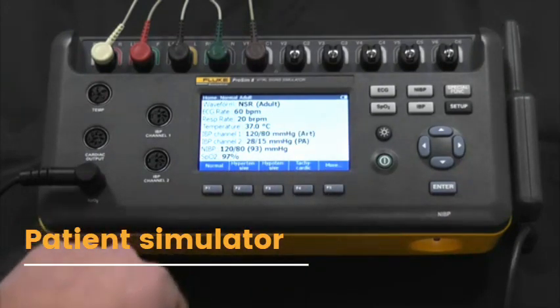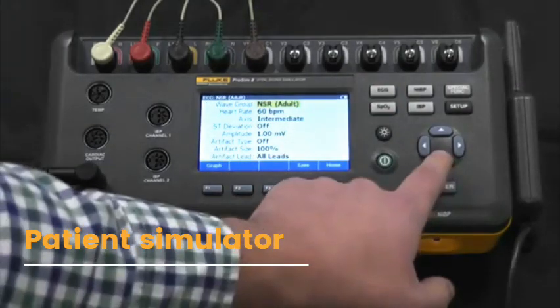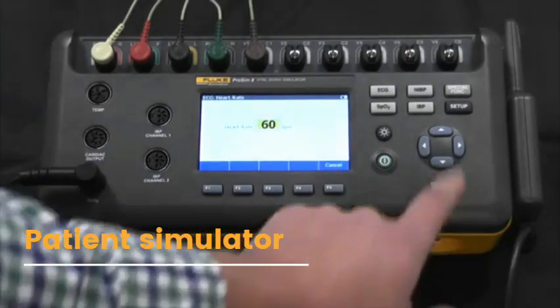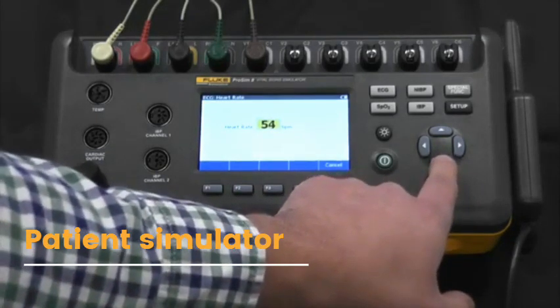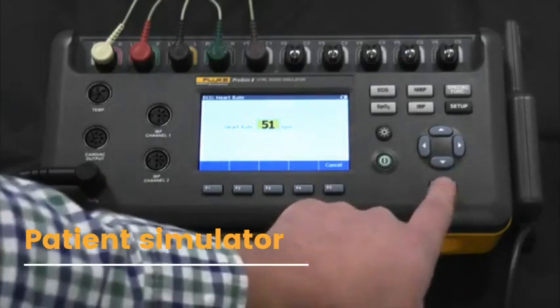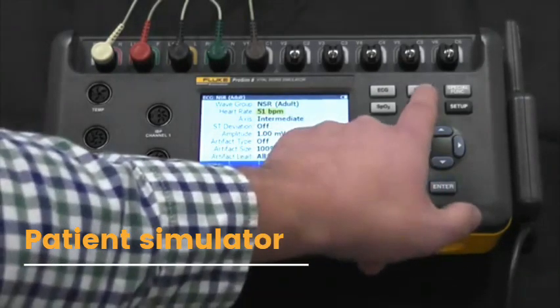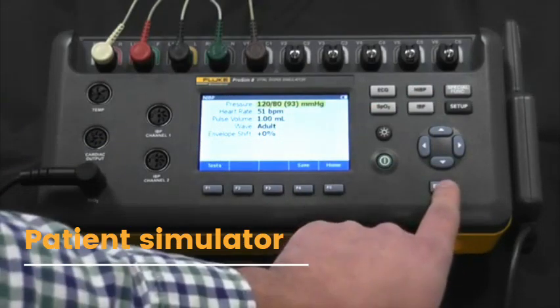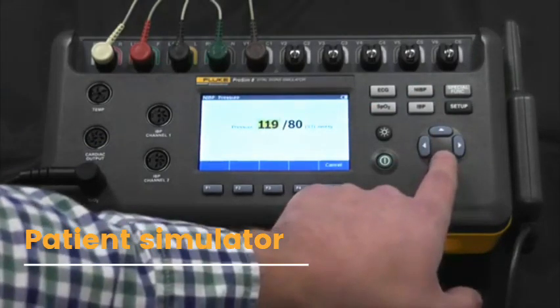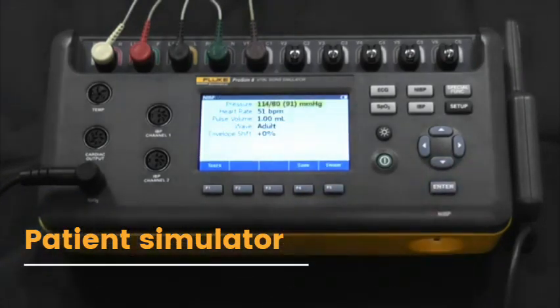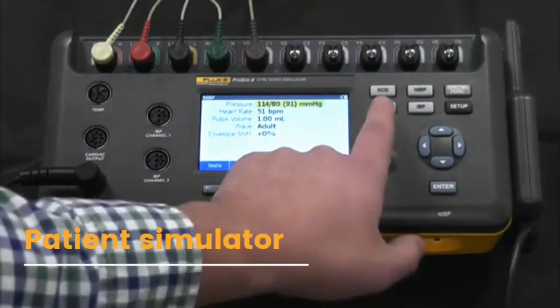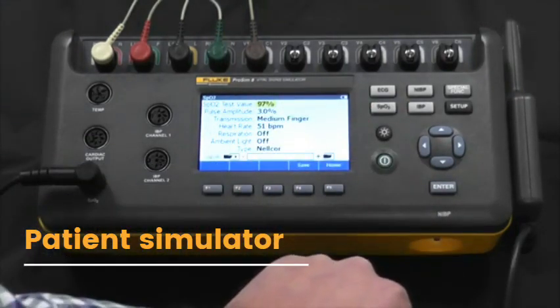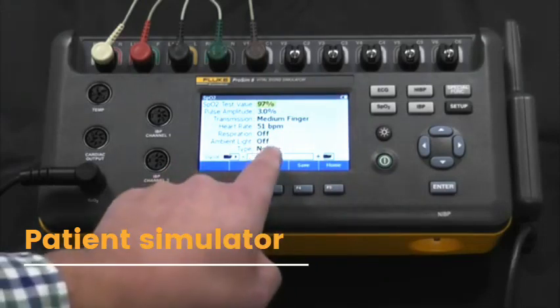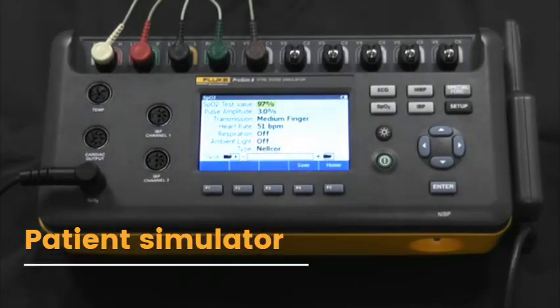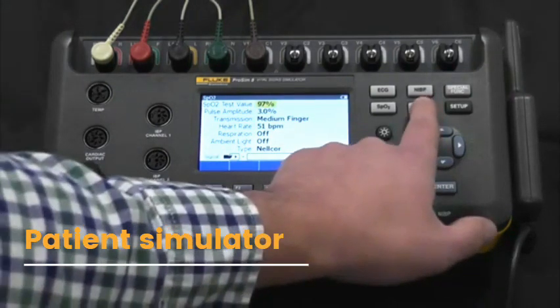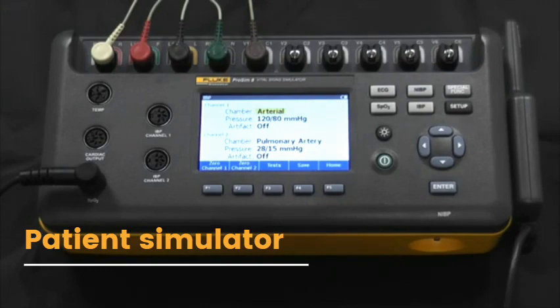So right now, we'll be in normal, we'll go to ECG, and we can adjust the heart rate to exactly what the patient monitor manufacturer states in their service manual. We can also do the same for NIBP by adjusting the blood pressure in 1 millimeter of mercury increments. We can also go through SpO2, where we can make the same adjustments, but we can also choose the type of pulse oximeter so that we're using the right curve. In IBP, we can choose the chamber, pressure, and artifact.